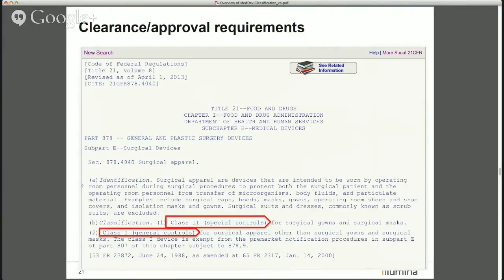Looking up regulation number 878.4040, the classification is listed right on the page. Surgical apparel is listed as a Class 2 device with special controls for surgical gowns and masks, but also as Class 1 general controls for surgical apparel other than gowns and masks. So here's a case where one regulation and one type of device has two different classifications and two different submission requirements.